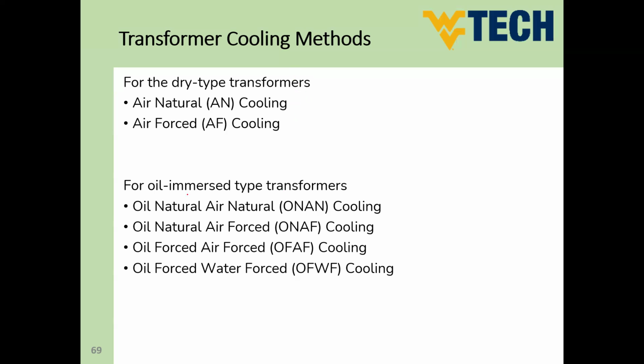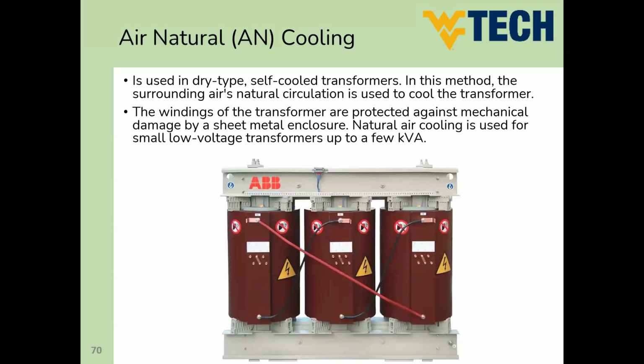Okay. We have also the oil immersed type transformers. So for the oil immersed type, you will find four different types here. We have what's called ONAN. So ONAN is oil natural air natural. We have oil natural air forced. We have oil forced air forced, and we have oil forced water forced coolings. So these are the most well-known four types of oil immersed type transformers. So let's see, guys, the shape of these types of transformers.